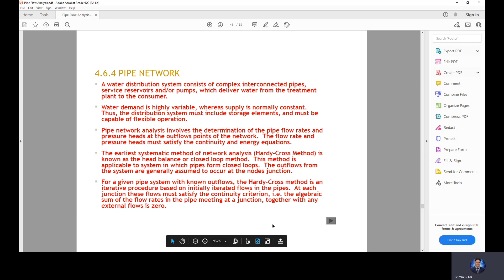So this is the process. Assign clockwise flows and associated head losses as positive. The procedure is as follows. Assume values of Q to satisfy summation of Q equal to 0. The algebraic summation of Q, how much input must be equal to the amount of output. The total inflow equals the outflow. Then calculate head loss from Q using h = KQ². Instead of applying the entire head loss equation, we just put in a head loss coefficient K. So head loss is equal to K times Q squared. The summation of head loss must be equal to 0, the algebraic summation. Then the solution is correct if it is 0.